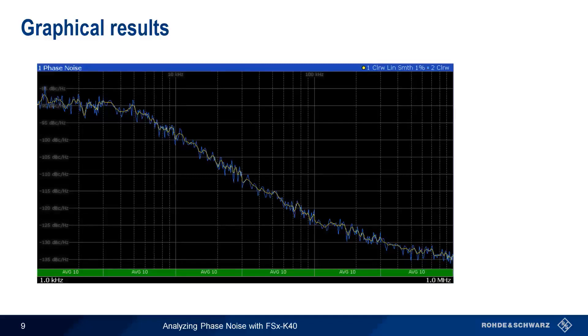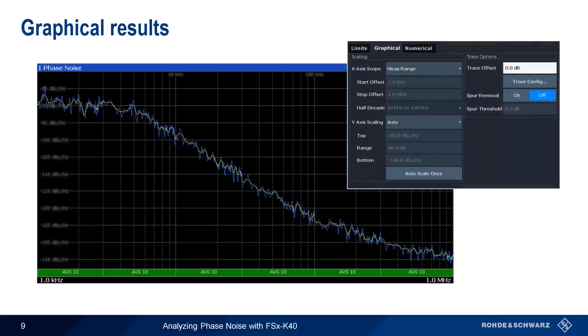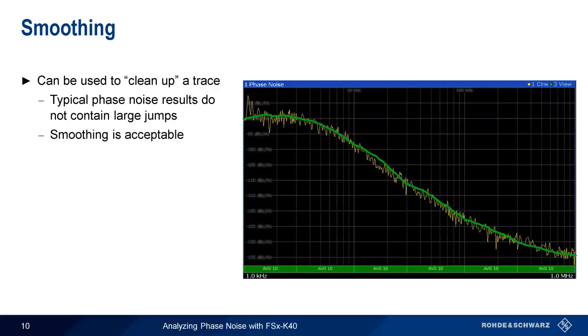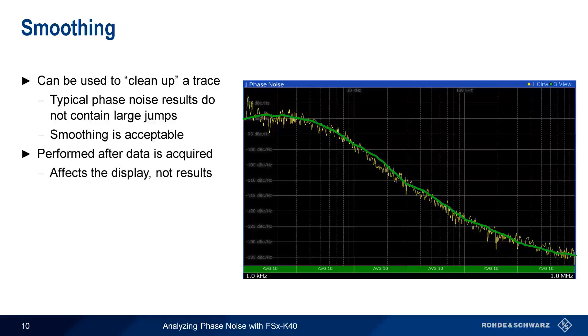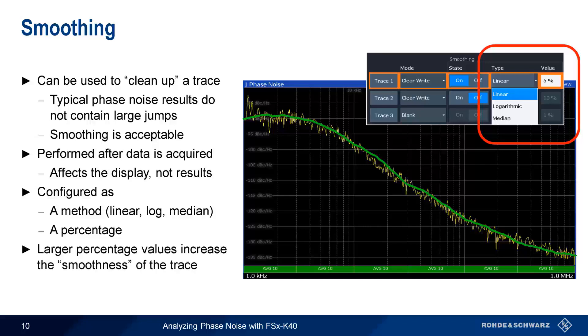The most fundamental phase noise measurement result is a semi-log plot of single sideband phase noise, giving phase noise power in dBc per hertz as a function of the offset. Results can be manually or automatically scaled. By default there are two traces: a raw trace in blue and a smooth trace in yellow. Smoothing cleans up the trace after data is acquired — it only affects how the data is displayed, not the actual results. Smoothing can be configured as linear, logarithmic, or median, with a user-specified percentage; larger values increase the amount of smoothing.